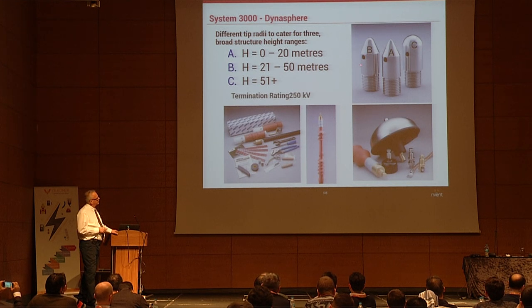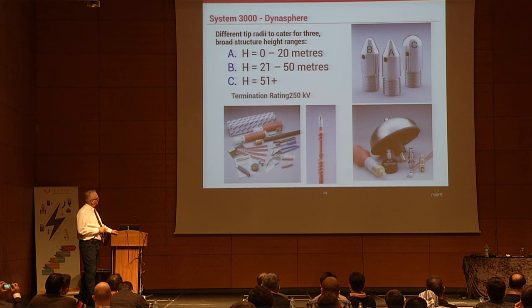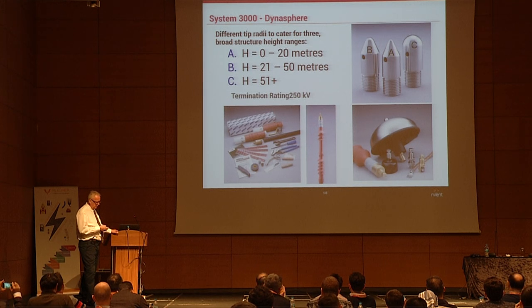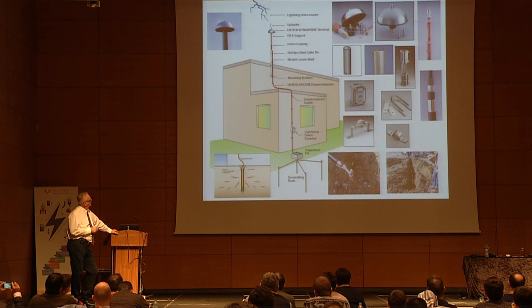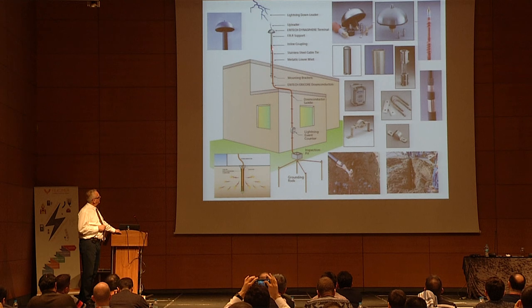The system components: a cantilever or guyed mast, a non-conductive mast going over the upper termination, and an inline coupler that allows the cable to exit the insulated mast. The system also includes lightning counters — if the system gets hit by lightning, it gets recorded.